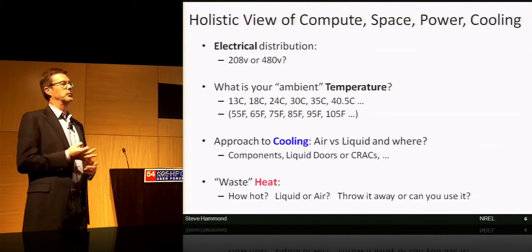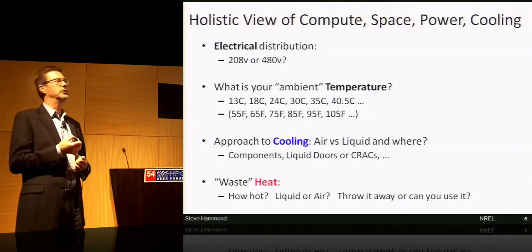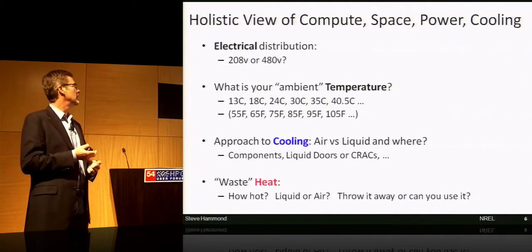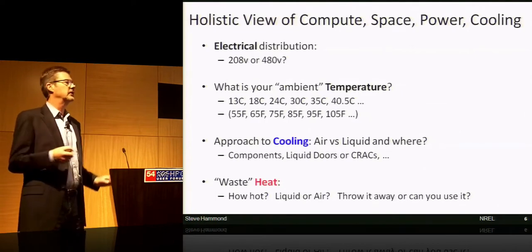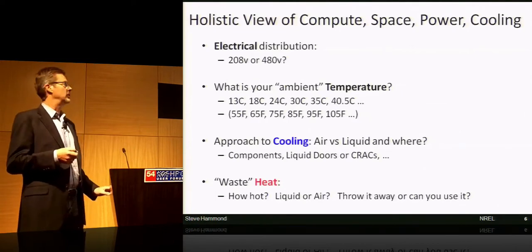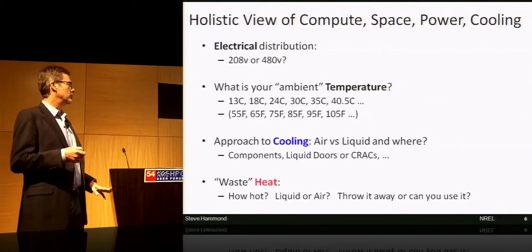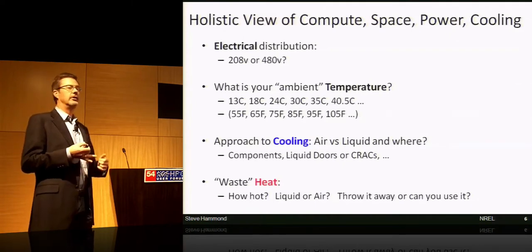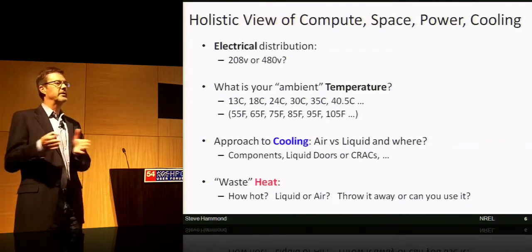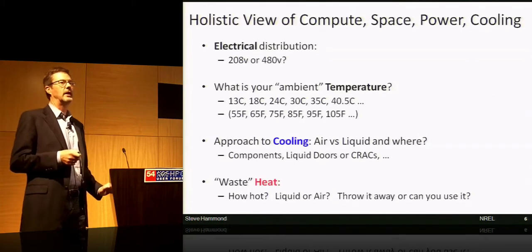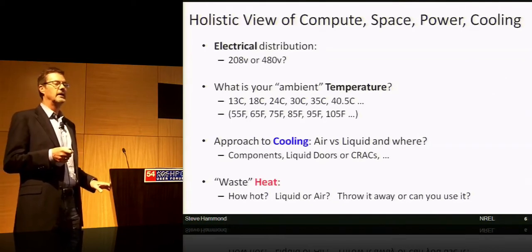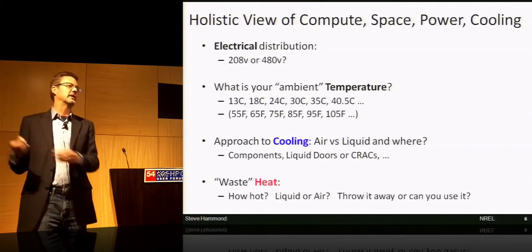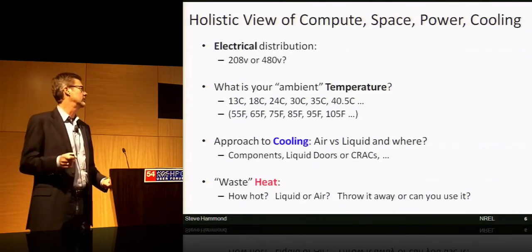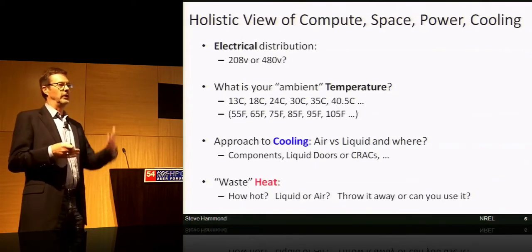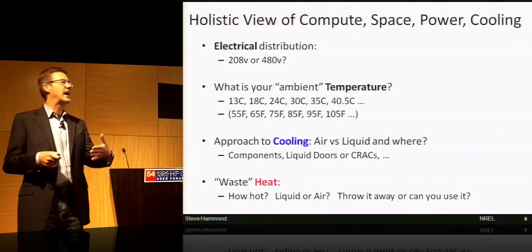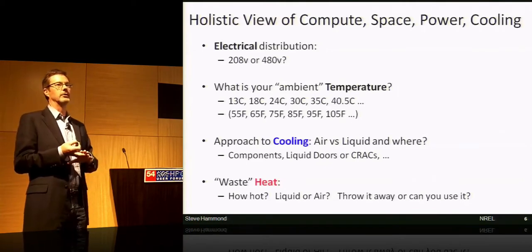Our considerations were on the power distribution: are you distributing 208 or 480 volt? What is your ambient temperature, which determines whether you need chillers? Your approach to cooling, air or liquid? And where does the heat exchange for your IT equipment occur? Does it happen at a CRAC unit outside the perimeter of the data center, at the rear door of your racks, or through component-level cooling?